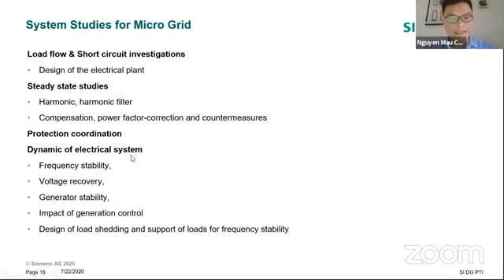And the dynamic study covers frequency stability, voltage recovery, generator stability, and the impact of generation control. Last but not least is the design of the load shedding scheme and support for frequency stability, because it's very important to take a very deep view in the microgrid. We need to make the priority list of the loads, because in the worst case you need to shed load, and you should shed the load with the lowest priority level. Then we can keep your microgrid surviving.